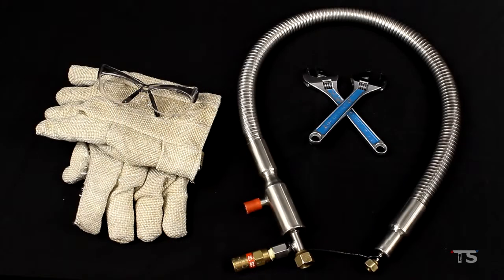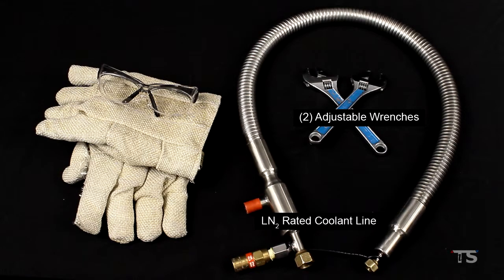To tighten the LN2 connections you will need two adjustable wrenches, an LN2 rated coolant line, and your personal protective equipment.